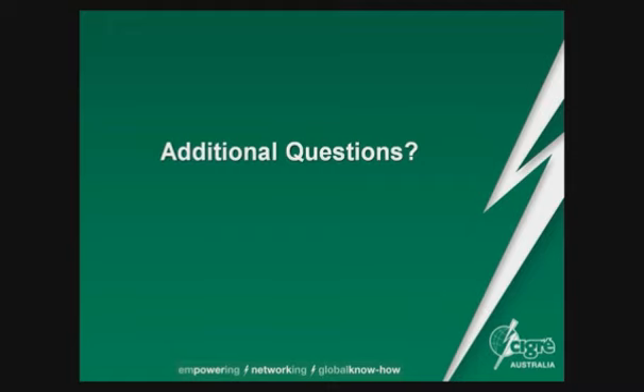Okay, so the first question there about load. So when we're making a connection or a disconnection, we don't have load. That's what I talked about when we're connecting a new bus bar. We make sure all the disconnectors off that new bar are actually open, because basically we look at the capacitance when we're making a new connection or disconnecting something.